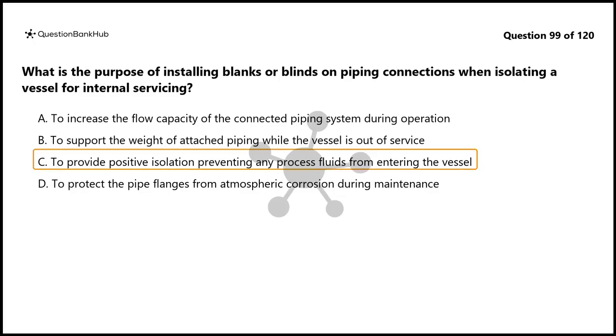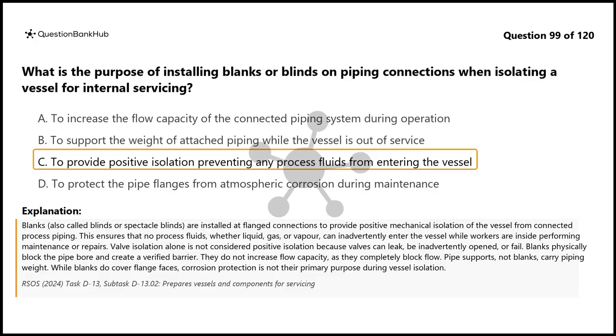The correct answer is C. Blanks, also called blinds or spectacle blinds, are installed at flange connections to provide positive mechanical isolation of the vessel from connected process piping. This ensures that no process fluids, whether liquid, gas, or vapor, can inadvertently enter the vessel while workers are inside performing maintenance or repairs. Valve isolation alone is not considered positive isolation because valves can leak, be inadvertently opened, or fail. Blanks physically block the pipe bore and create a verified barrier.